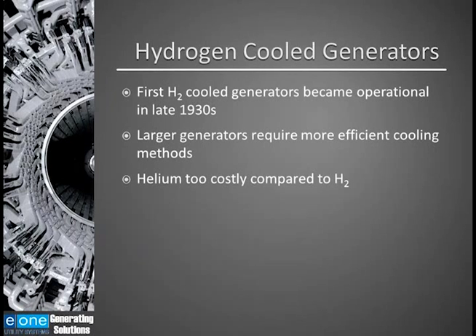In the late 1930s, there was an increasing demand to get more megawatts out of power generators. With generators, more megawatts means more iron. They get physically larger and generate more heat. In order to satisfy the demand for power without increasing the physical size of the generator, a different method of cooling was required. Imagine using a very explosive gas like hydrogen to cool a large machine that has components that are spinning at a very rapid speed. I find it very interesting that someone decided it would be a good idea to cool a generator with hydrogen. However, the idea worked, and now all large generators are cooled with hydrogen or a combination of water and hydrogen.